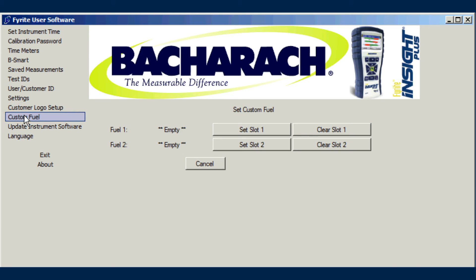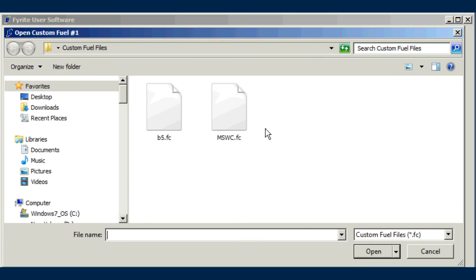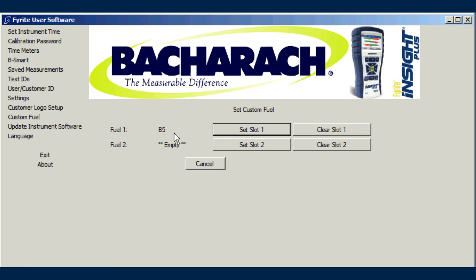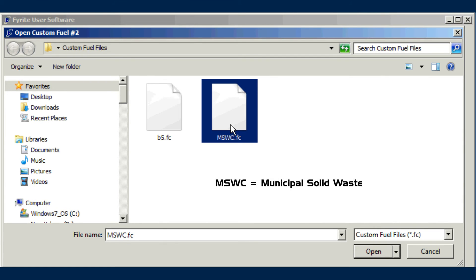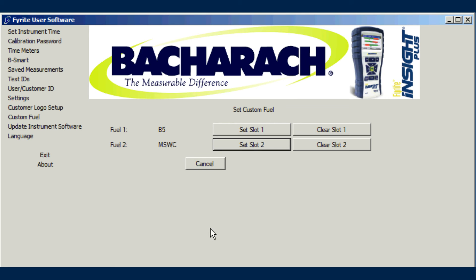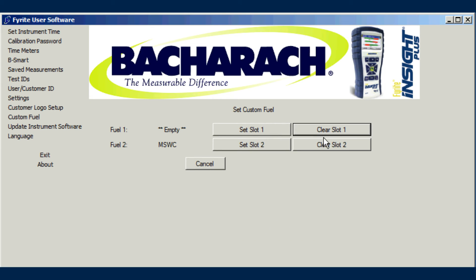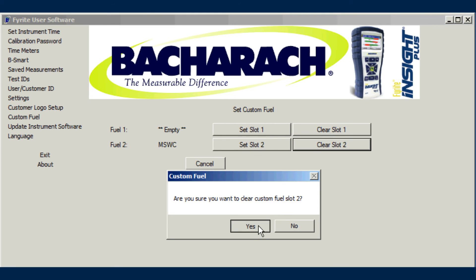Bacharach combustion analyzers support various combustion fuels. If your application uses a fuel not supported, one or more fuel equations may be added to certain instruments. Use the Custom Fuel screen to download a custom fuel data file to your analyzer. If you have a custom fuel application, contact Bacharach technical support to request a fuel file. Use the Set buttons to select the fuel from your PC and download it to your combustion analyzer. Once downloaded, you can select that custom fuel from your fuel menu. If you have two custom fuels loaded and need to add another, you can remove a fuel using the Clear Slot button.